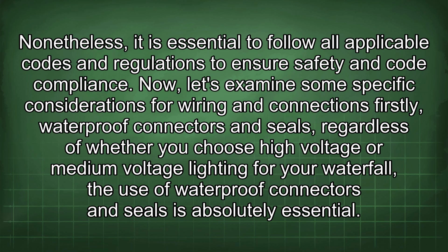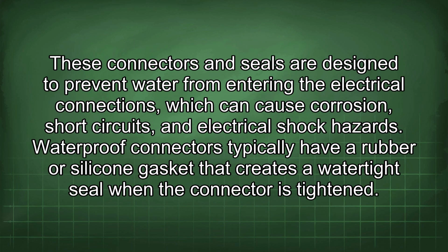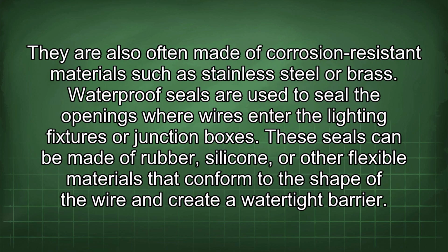Firstly, waterproof connectors and seals. Regardless of whether you choose high voltage or medium voltage lighting for your waterfall, the use of waterproof connectors and seals is absolutely essential. These connectors and seals are designed to prevent water from entering the electrical connections, which can cause corrosion, short circuits, and electrical shock hazards. Waterproof connectors typically have a rubber or silicone gasket that creates a watertight seal when the connector is tightened. They are also often made of corrosion-resistant materials such as stainless steel or brass.